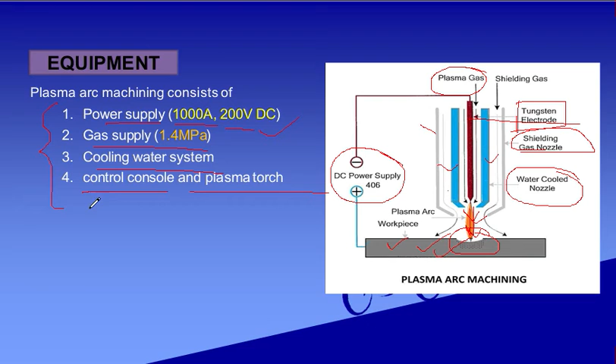So what is the equipment that is considered here? Power supply, which should be between 1000 to 2000 ampere and up to 200 volt, that is the DC volt. Gas supply should be around 1.4 megapascal, and a cooling water system must be there. A control console and a plasma torch are also used. So these are the basic equipment that you are using.